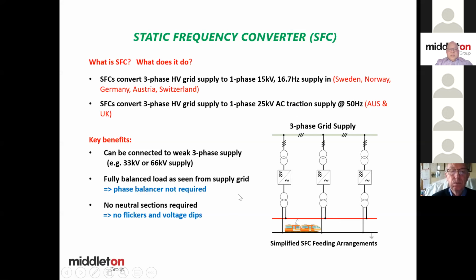So what are the key benefits? I've just got a little figure to show you here. You can connect it to a weak supply, 33 kV or 66 kV. But because you're taking supply from 3-phase, the load is balanced as far as the grid is concerned. You then convert that to DC and then DC to single phase AC to feed the railway. Because these are all power electronics equipment, you can actually make the output phases exactly in phase. So you eliminate the need for a neutral section between them. It's just like DC, except it's 25,000 volts. So this is a rail return system, 25,000 volts.